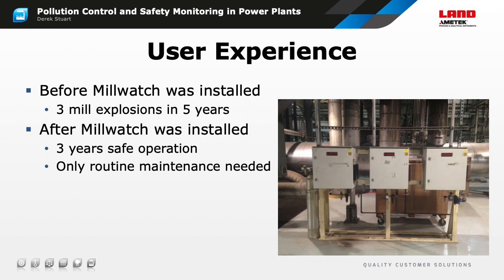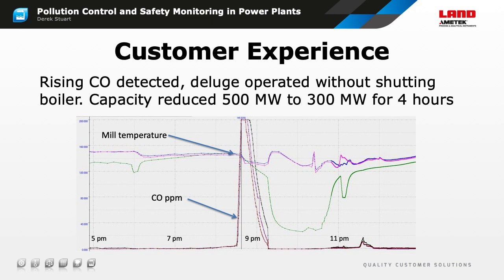The first example is a site which had 3 mill explosions in the space of 5 years and decided to install AMETEK Land Millwatch CO monitors. They burn subbituminous Powder River Basin coal, which is well known for its propensity for self-heating. After installing the Millwatch analyzers, they ran for 3 years with no explosions, and so far as I'm aware, they're still running safely and successfully. Here's a graph showing how a hazardous condition was identified and made safe without shutting down the boiler. The image shows the CO concentration and mill temperature.